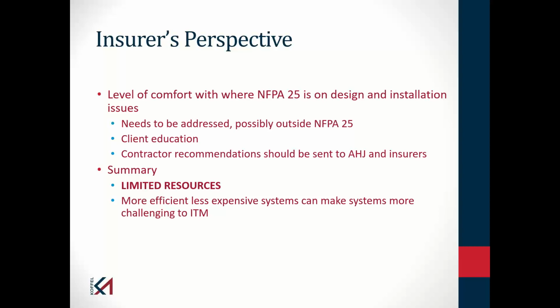Now, the contractor who did the inspection activity said, not my job, outside my scope, that's a design issue. However, this person actually owned a couple of health clubs, and during the litigation, it was noted that the contractor actually did provide recommendations or comments on design issues in other buildings. So the court found in favor of the owner, saying the contractor was providing a different level of service in some of these buildings, and felt that the contractor probably should have at least called it to the attention of the owner. You know, as the inspecting contractor, I might not know that it's a violation. Maybe somebody got a variance from the local jurisdiction or something, but at least make a comment, an observation, that we observed there was no sprinkler in the sauna.